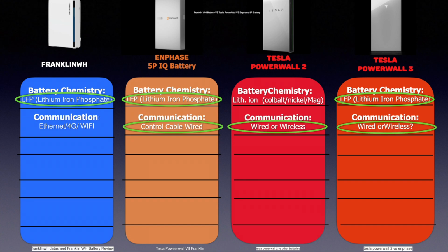Let's talk about communication. We actually prefer a wired connection in most cases, because at a job site sometimes you can't get a good signal, or say the battery has to go behind a wall. A wired connection is actually preferred and more reliable. In this case, I've given the green circle to both Enphase as well as the Powerwall 2 and 3. It's not bad to have a wireless connection, but it's just a little bit less reliable in certain areas where you don't have good reception.